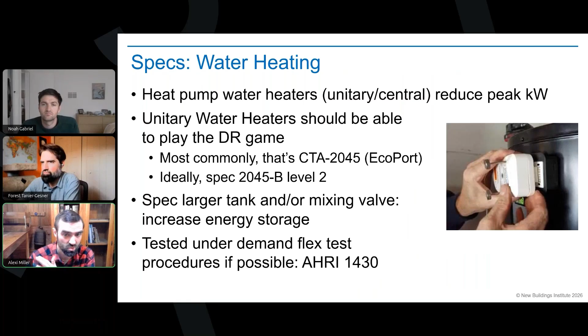Or use a mixing valve that allows you to heat the water up to, say, 140 degrees, then make sure that 140-degree water never gets out into the pipe, so there's no scalding risk. It's another way to increase the amount of energy stored in the system - just store it hotter.